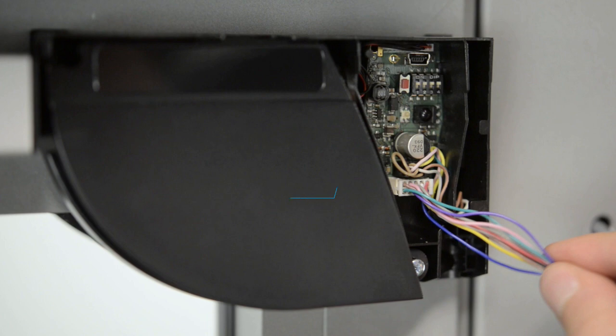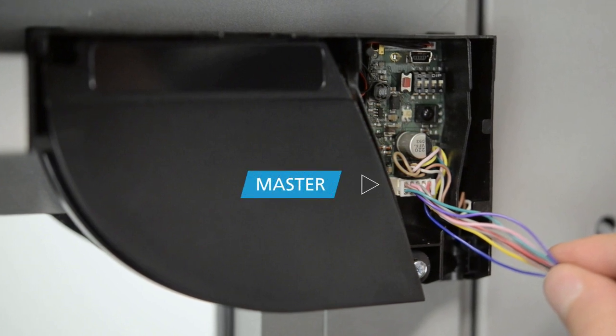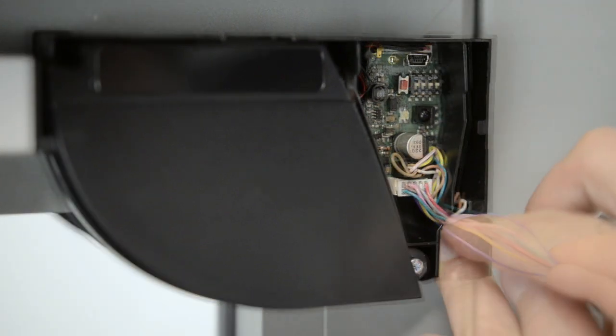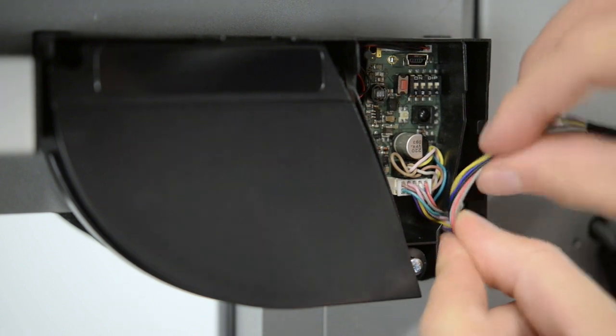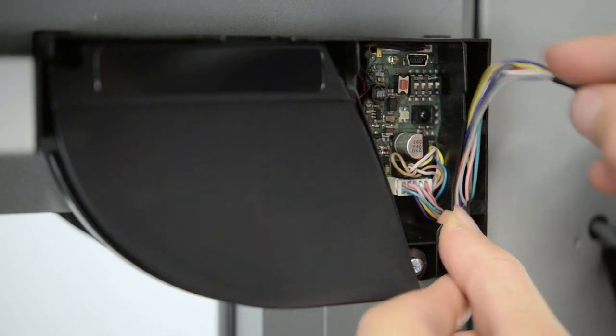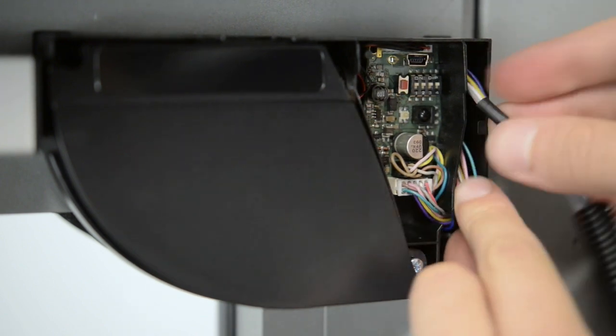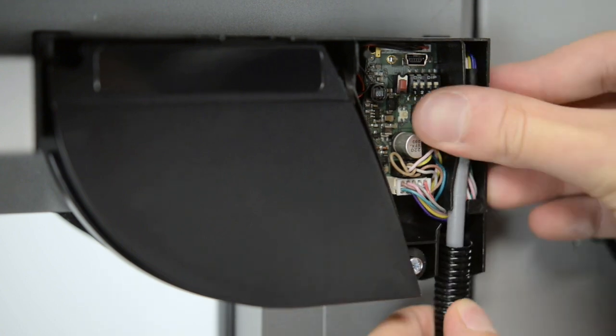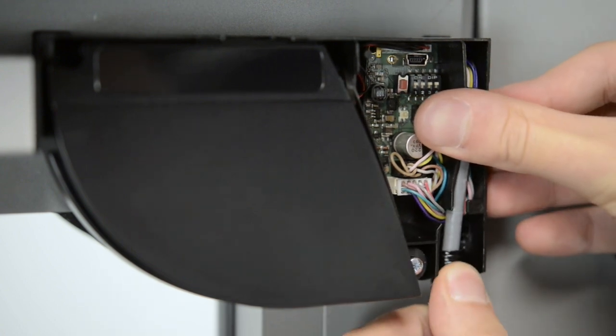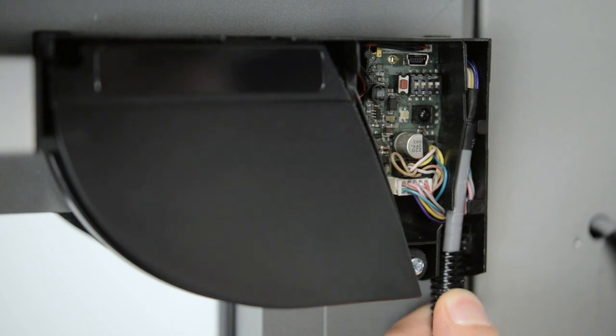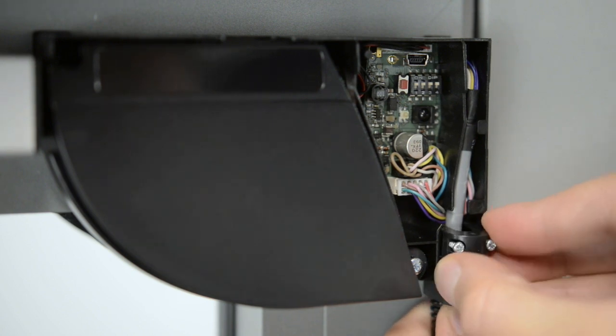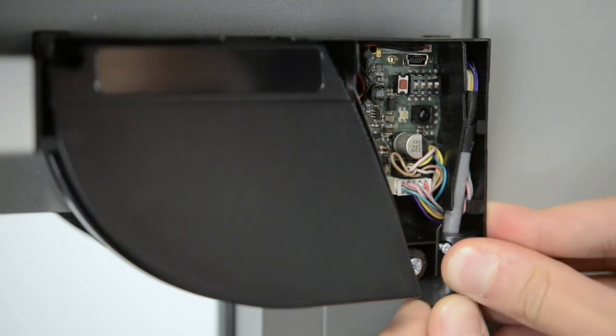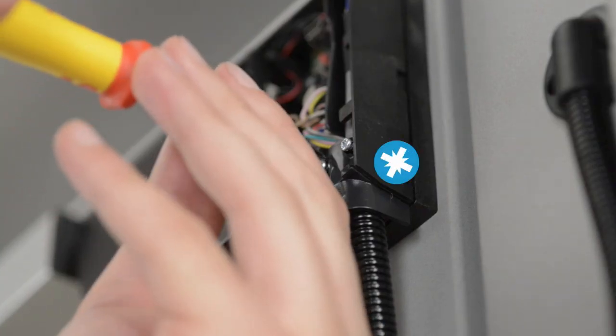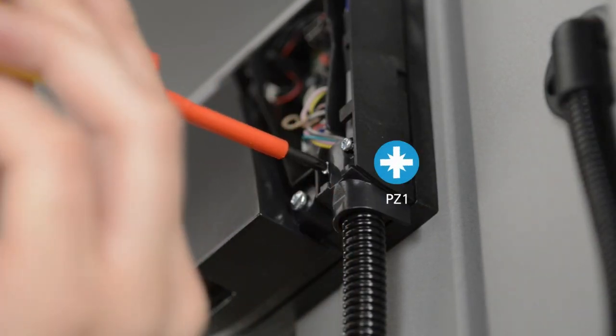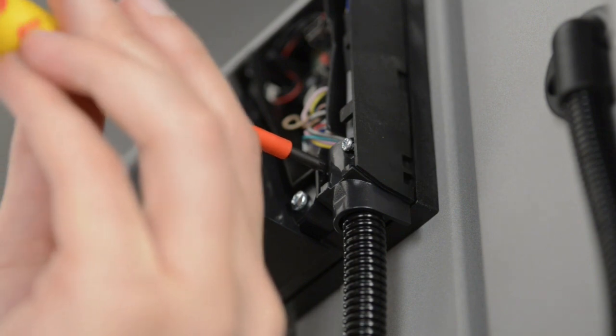The sensor that is connected directly to the door controller is the master module. Make a loop with the wires of the power cable and pass them through the notch as indicated. Use the other part of the cable to block the wires. Take the clamp to fix the flexible tube to the sensor. Fasten the two screws firmly in order to avoid pulling out the cable.